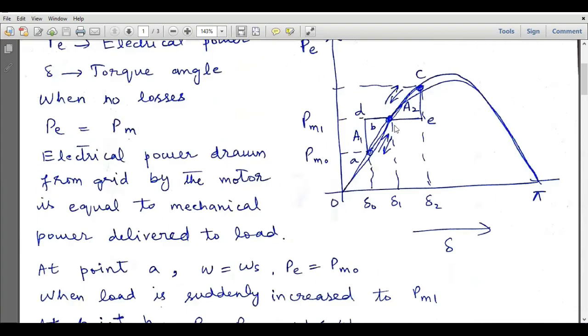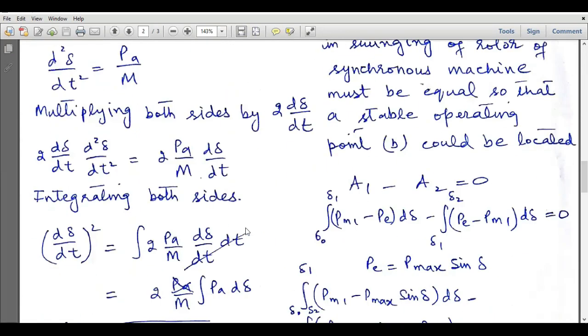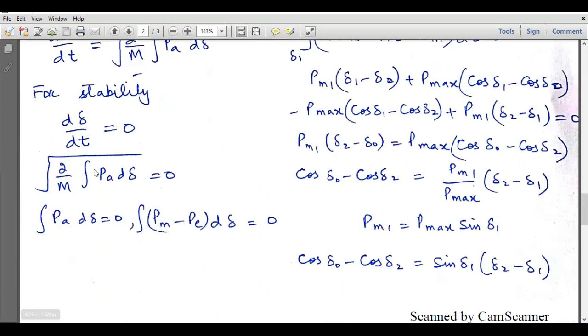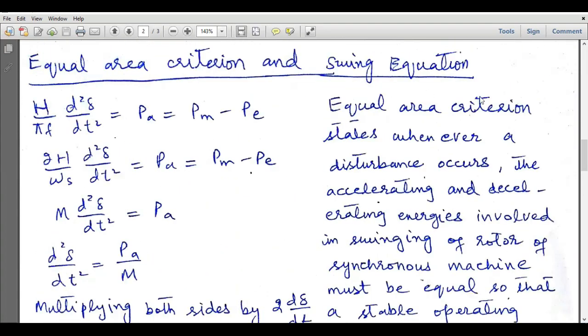If the system is stable at point B, there are no more oscillations, delta becomes constant, and d_delta/dt equals zero. This is the condition for stability: d_delta/dt equals zero means ∫pa · d_delta equals zero, and since pa equals pm minus pe, we need ∫(pm − pe) d_delta = 0. The equal area criteria can be defined as: whenever a disturbance occurs, the accelerating and decelerating energies involved in swinging of the rotor must be equal so that a stable operating point B is located.